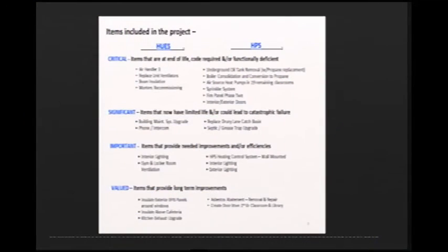First is air handler number 3, which sits on the roof at Hollis Upper Elementary School. It's been jury-rigged over the years to keep operating. Ed has done a great job keeping it running, but it has problems. It goes into unoccupied mode at times and shuts down, and when that happens, cold air can come into the building and downstream through the pipes and conduit, freezing the variable air volume boxes below. When that happens, we could break water pipes, and in the music room, cafeteria, or office area there could be a disastrous flood. So this is very critical to get done.